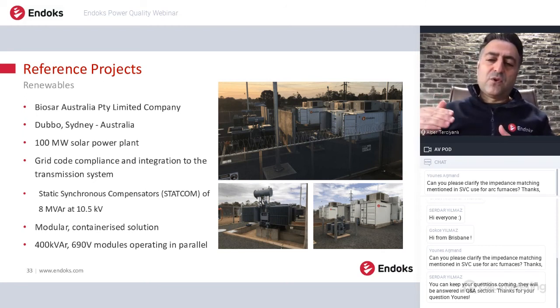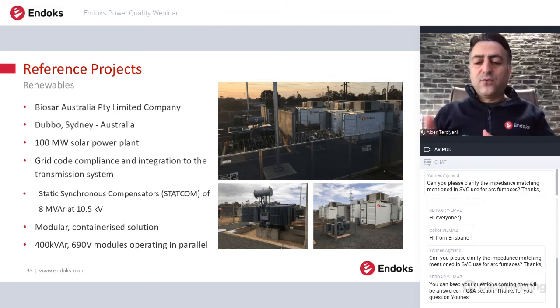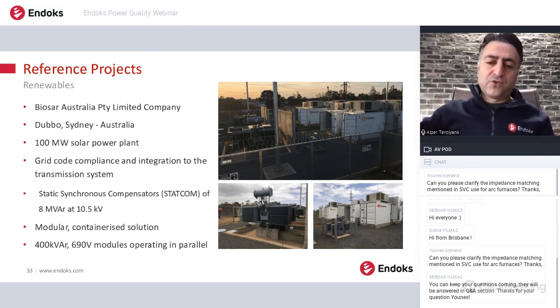Actually, the rated voltage of the converter is 690 volts, but the operating voltage is 480 volts. So each module is 400 kVAR at 480 volts, and it becomes 8 megawatt on the medium voltage side. And as I told previously, in the STATCOM, for example, we can inject 16 megawatt, 2 times rated power, for 3 seconds. So if there is a fault in the power system, maybe a short circuit or a heavy load switching, so the voltage is rising or oscillating, this STATCOM can inject more power to support the grid in terms of voltage.